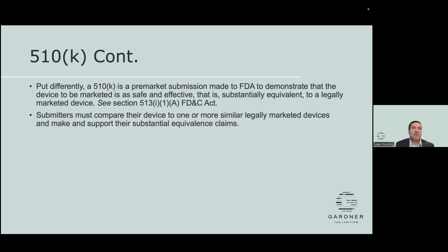And so in a 510(k) sense, you're making a premarket submission to demonstrate that it's as safe and effective as a legally marketed device. So you have to do a comparison of your device to a device already on the market. And when you're talking about artificial intelligence, you can see how that can become difficult because of the purpose of AI, of ML, right? It's unique. Is it different from something on the market? And so having a good argument, a good basis for your substantial equivalence discussion with FDA allows you to get to market faster, right? Because from an FDA review standpoint, a 510(k) is your fastest path to market.